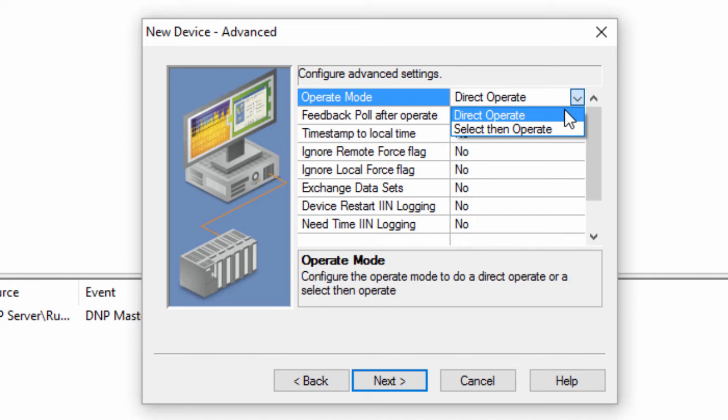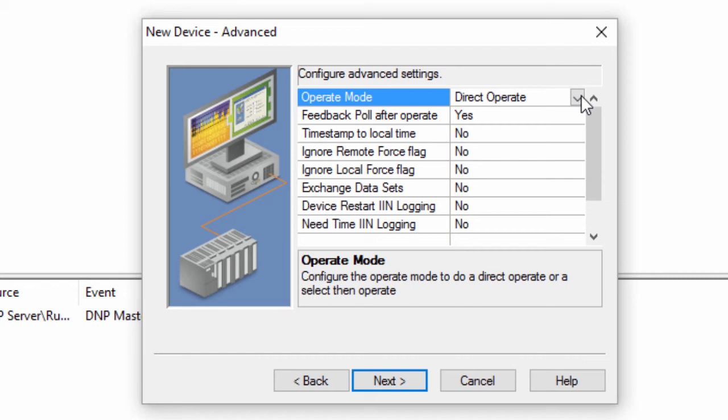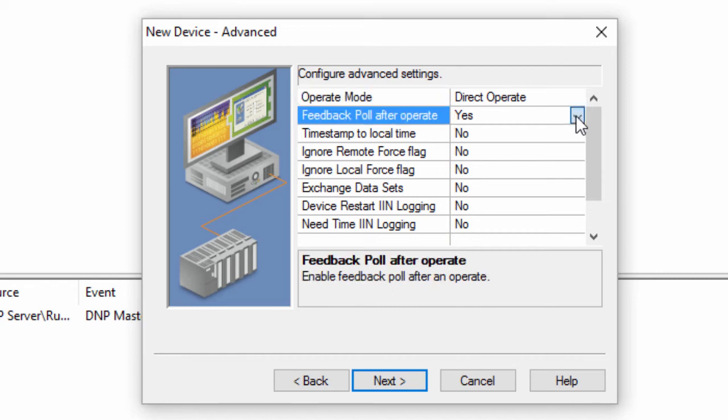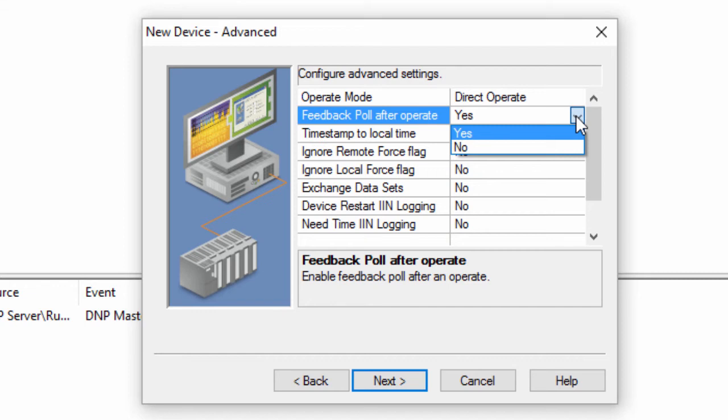With direct operate, you write directly to the value subtype. The default behavior is direct operate, which many if not most slaves support. In normal operation, after writing to a slave, a DNP master will perform a feedback poll of the slave. We have found that this causes problems with some slaves. This setting allows you to turn off this feature.